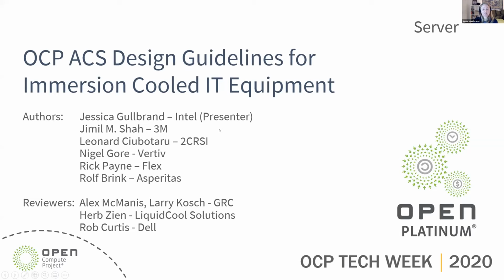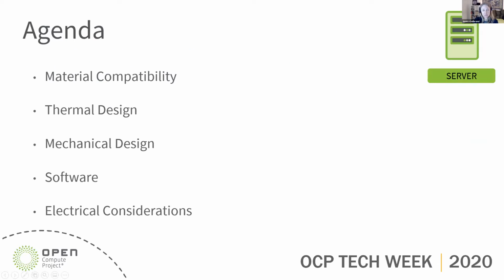So the aim of this white paper is to address the design considerations that are different when it comes to immersion cooling. The community is generally very familiar with air cooling, but in immersion, if you're taking a system and putting it into a liquid, there are some other design considerations that you need to be aware of. Specifically, the ones that we're addressing in this white paper are the following five: material compatibility, thermal design, mechanical design, software, and electrical considerations. So if we jump into it directly, I'll just give a very high level overview of these five different topics.